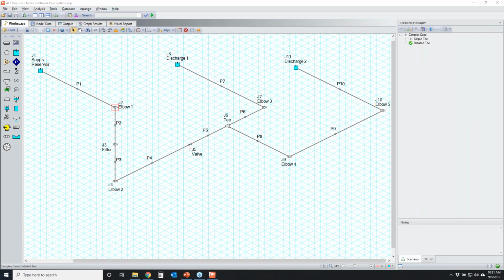Okay, so in Fathom, I actually had elbow junctions all throughout the model. Well, we don't have elbow junctions in Impulse because people would be tempted to use them, and they do not cause any transient behavior to happen because you can't change the position of an elbow over time. It's just going to stay there. So it's best to lump in your elbows as additional fittings and losses into a single pipe itself.